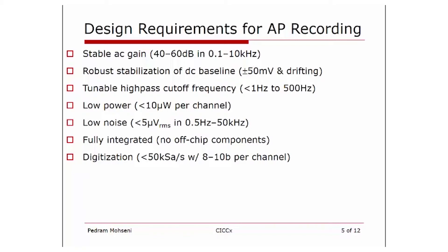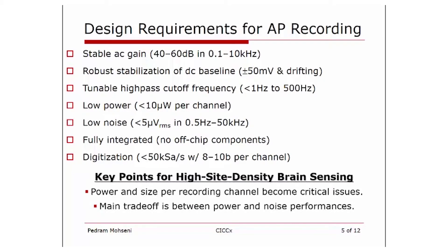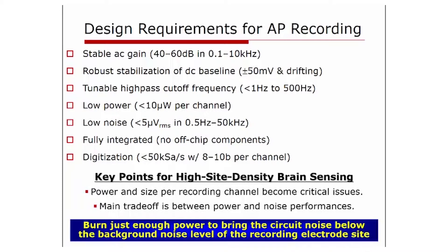The current trend in brain sensing is toward high-site-density recording where you may want to simultaneously record from hundreds if not thousands of channels. Power and size per recording channel become critical issues in high-site-density recording. Given the higher-frequency nature of action potentials, your front-end design will typically be limited to thermal noise, creating a trade-off between power and noise performance — burning more power brings the noise level down. A good rule of thumb is to burn just enough power to bring your circuit noise below the background noise level of the recording site, which is typically about 10 microvolts RMS depending on the area of the site.